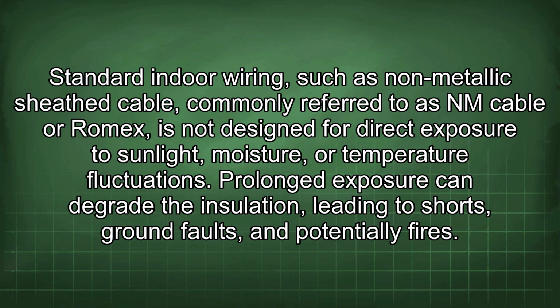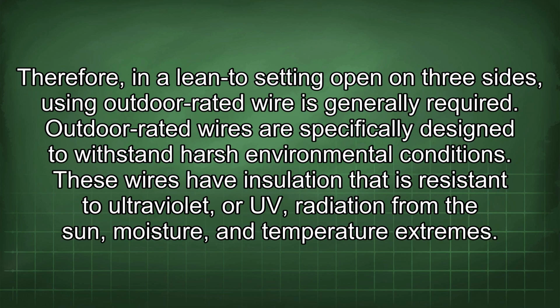Standard indoor wiring, such as non-metallic sheathed cable, commonly referred to as NM cable or Romex, is not designed for direct exposure to sunlight, moisture, or temperature fluctuations. Prolonged exposure can degrade the insulation, leading to shorts, ground faults, and potentially fires. Therefore, in a lean-to setting open on three sides, using outdoor rated wire is generally required.